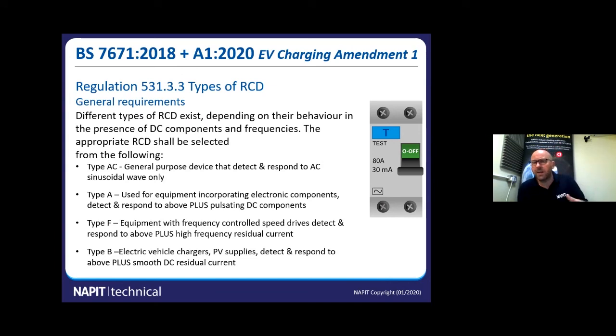So the type AC is the basic one that we've had for years and years, and they're starting to be replaced now with type A's and F's and B's. A type A device will work up to 6 milliamps DC leakage, a type F will be 10 milliamps, and a type B does everything. So that's the kind of hierarchy of them. The type B is the best and the type AC is the worst.